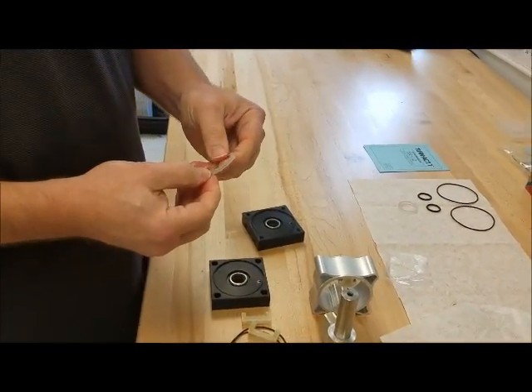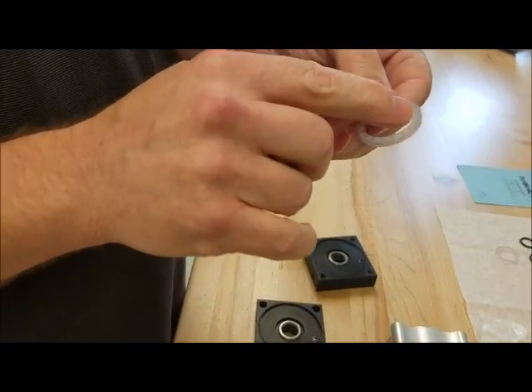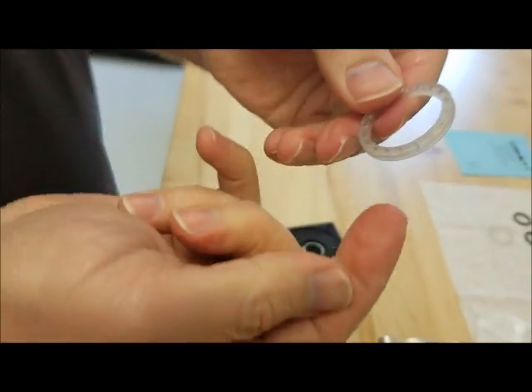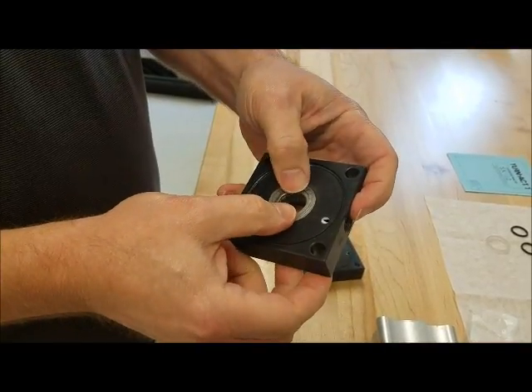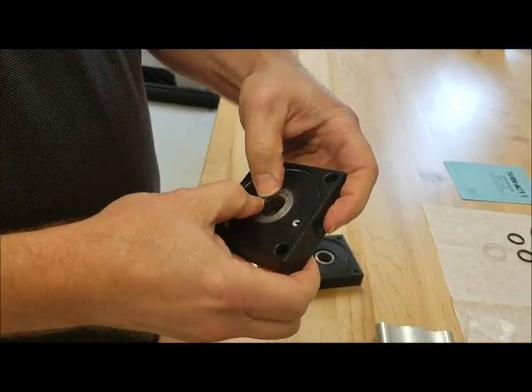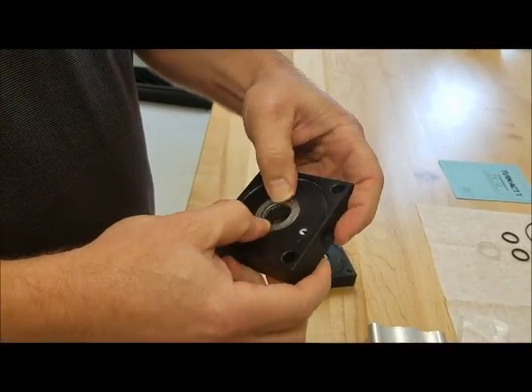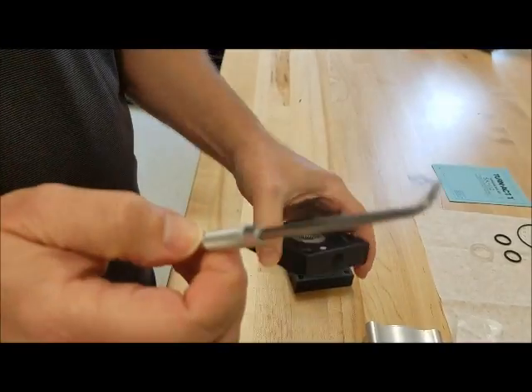On your end caps, we're going to start with the quad ring. And the quad ring has holes on one side of it. You want to make sure those are up. So what we're going to do is we're going to place the quad ring in the groove. We're going to get it to seat the best we can. And then this is where the pick comes in.